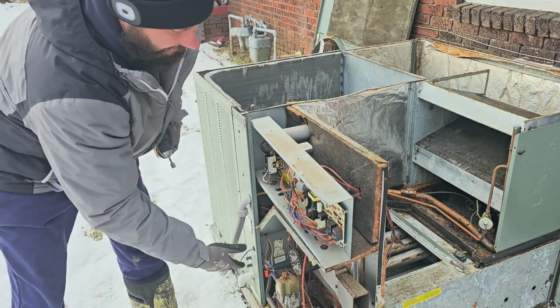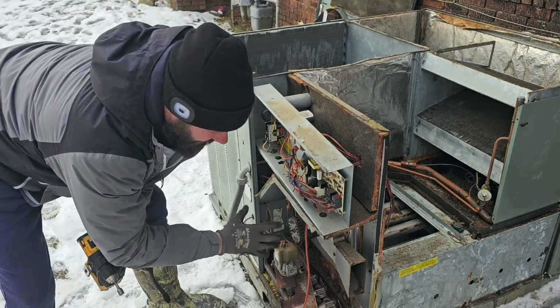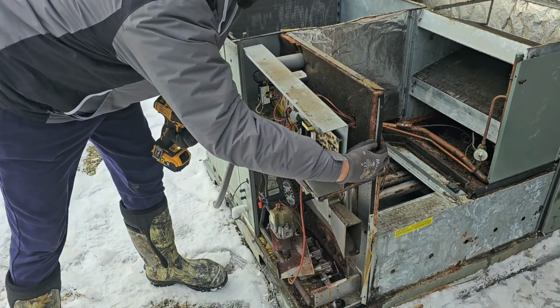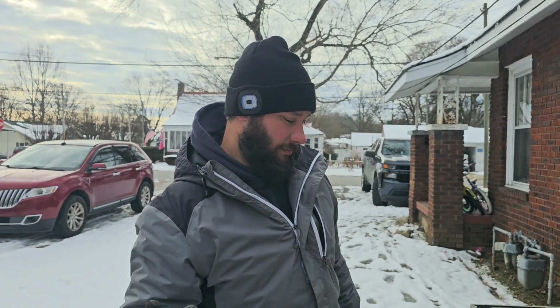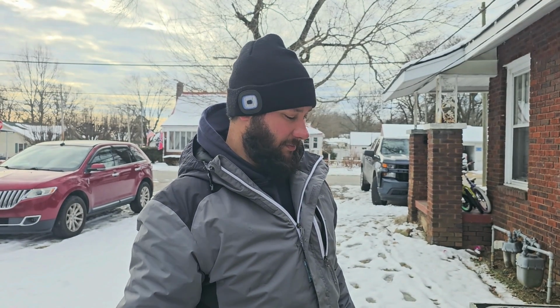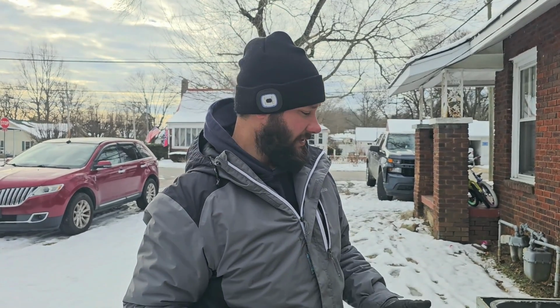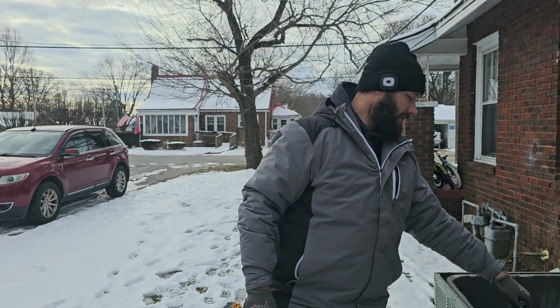We need to get this panel out of the way, and we need to take basically everything off of the front of this heat exchanger. Your inducer motor, your flue box cover, your burner assembly, your manifold pipe off of the burner assembly. You may need an extension for your drill at this point. And we also have to take this PVC pipe loose and take that screw out.